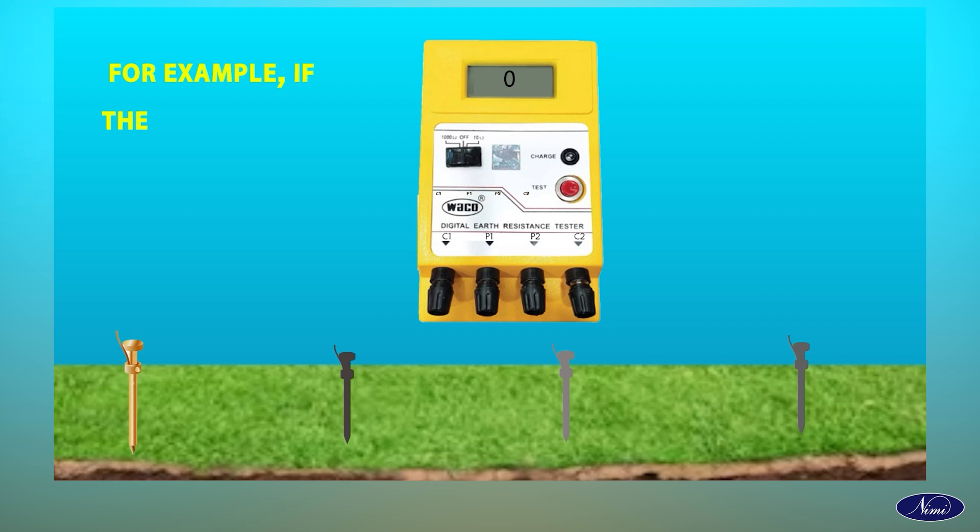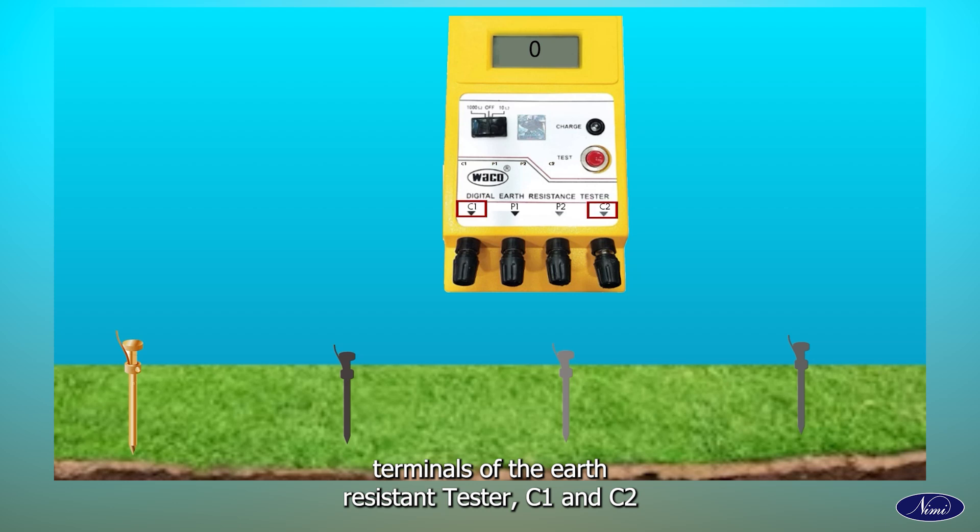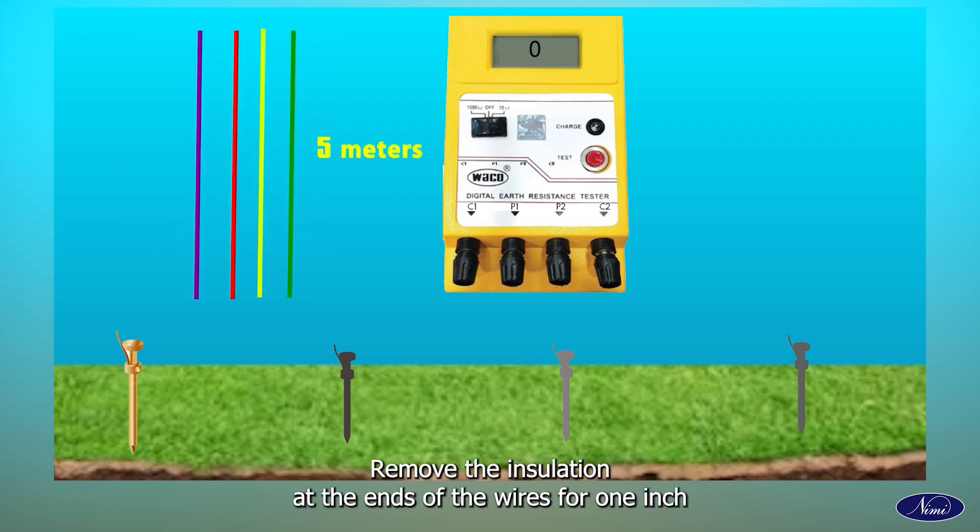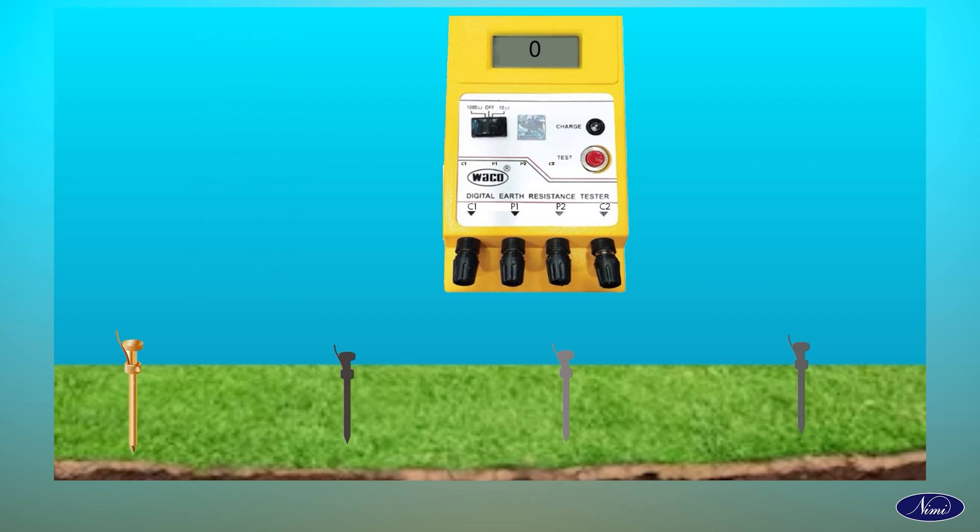For example, if the depth of each Earth electrode is 1 foot, then the distance between electrodes is greater than 20 feet. Mark the current terminals of the Earth-resistant tester as C1 and C2 and the potential terminals as P1 and P2. All four wires should have the same length of 5 meters each. Remove the insulation at the ends of the wires for 1 inch and connect all the four wires between the four terminals.